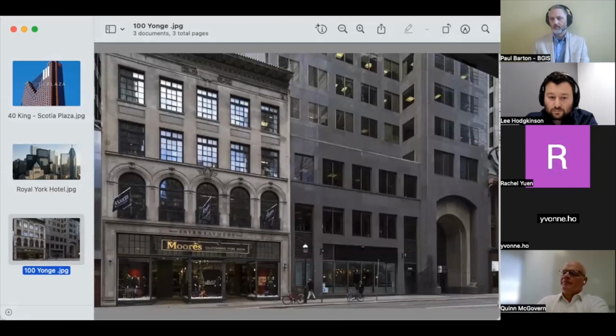It's a smaller building attached. It's about a 300,000 square foot building. We flipped it entirely to air source heat pump. We had end of life boilers, end of life chillers. We put in a dual stage air source heat pump where we're running variable refrigerant units on the roof into a booster unit. We did not go into any of the spaces. This is capable of outputting 180-degree Fahrenheit water to power anything we need in the building.